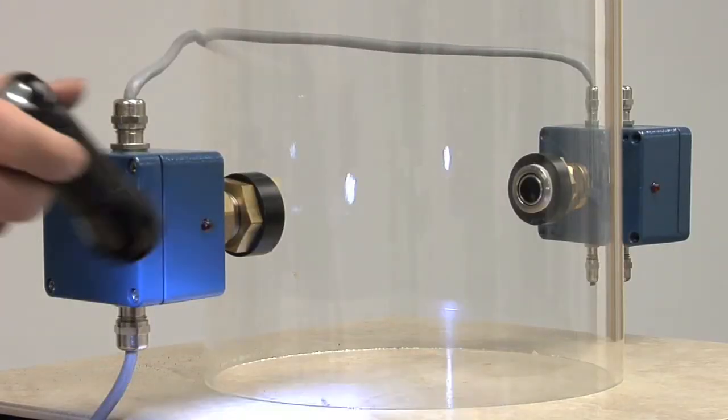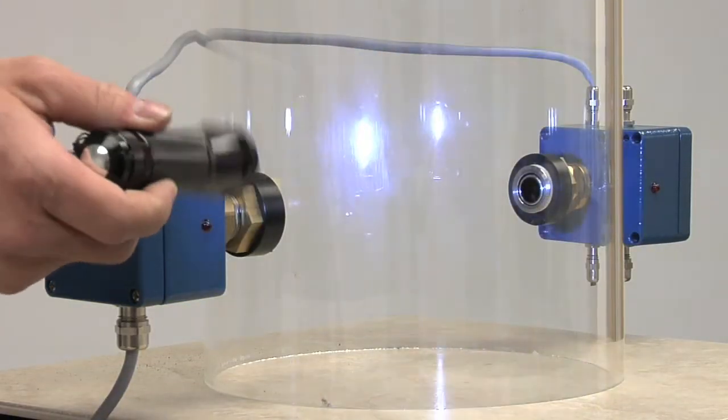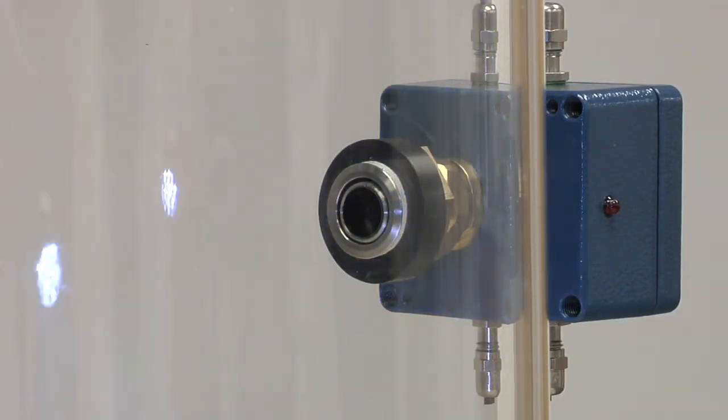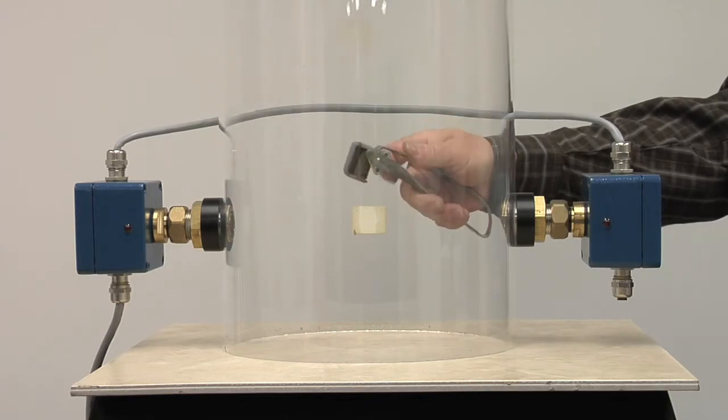This detector responds to infrared in the 1.3 to 2.7 micron range, which allows it to be impervious to most ambient light while still being able to sense dangerous sparks.